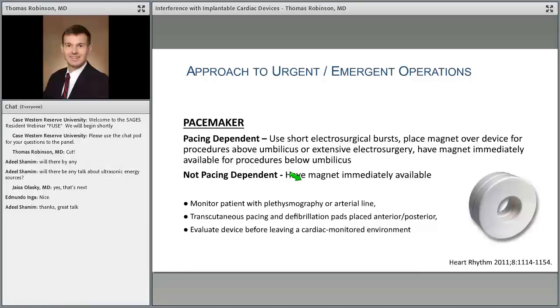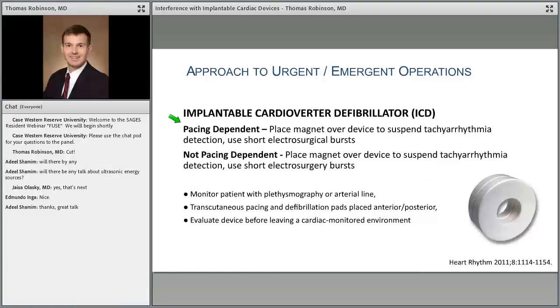So the next slide has the same monitoring, which is down here, but it's going to change the management strategy because it's now a cardioverter defibrillator. So this was the one with the large radiopacity towards the tip of the lead. That's that coil that stores the charge. All right, so for a pacing-dependent patient, place the magnet over the device to suspend tachyarrhythmia detection and use short electrosurgical bursts. And then the second would be for a not pacing-dependent, place a magnet over the device to suspend the tachyarrhythmia detection and use short electrosurgery bursts. So this would be a reasonable algorithm to use if you're in the middle of the night and you do not know what kind of device the patient has.